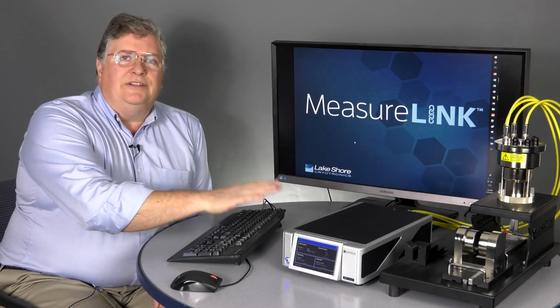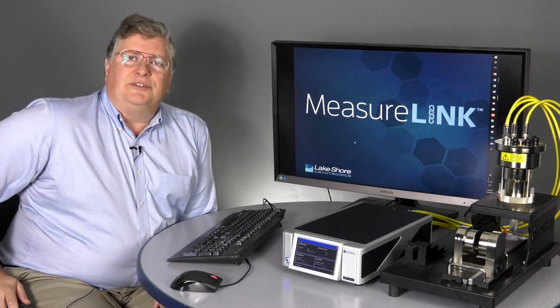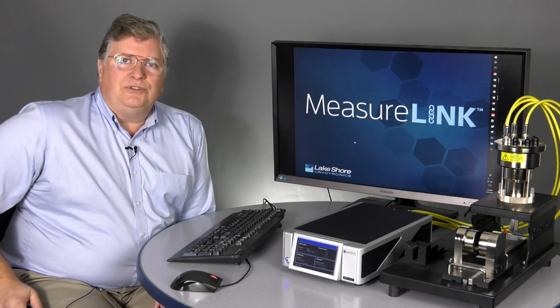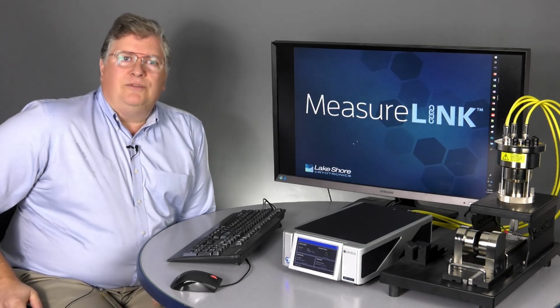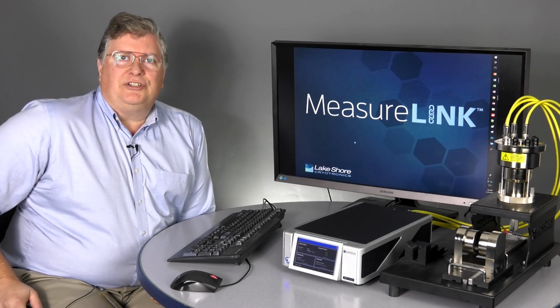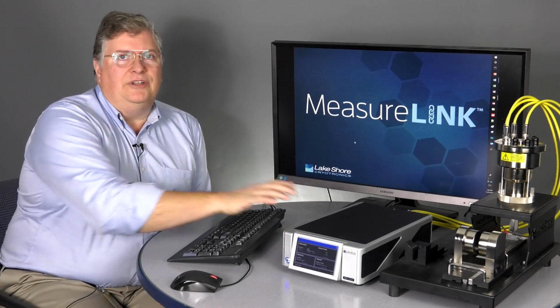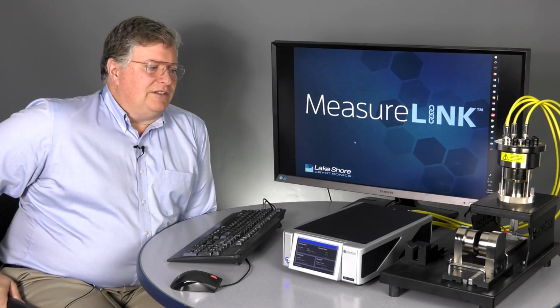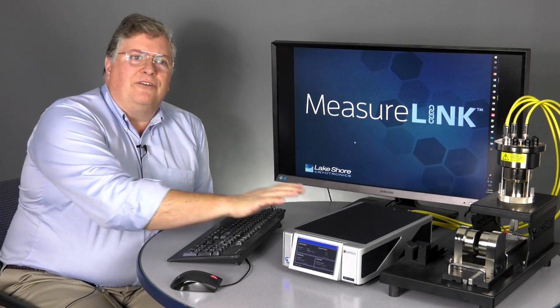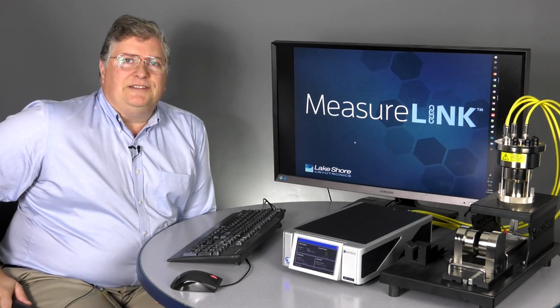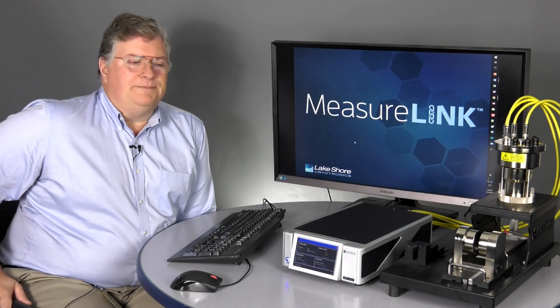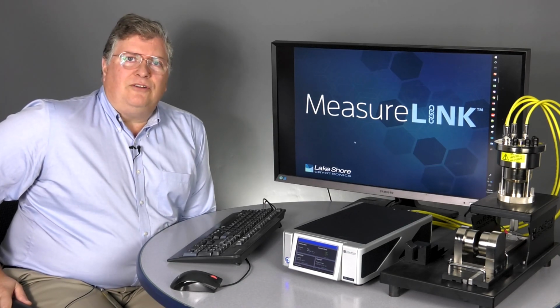The M91 is an all-inclusive Hall measurement instrument. It combines a voltage source, current source, voltage and current measurement, switch, and analysis all in a single unit. This allows us a very easy platform for integrating an existing measurement or as the basis of a new Hall measurement system. I used the term FastHall earlier.